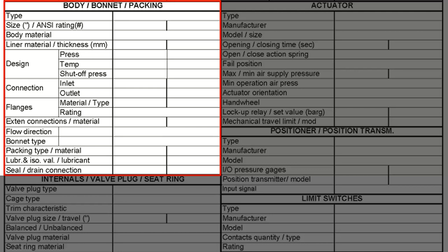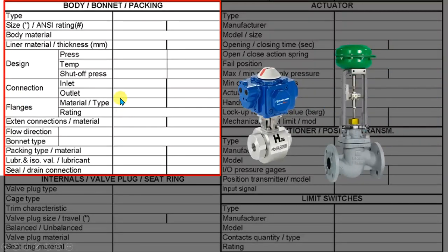In the European context, size and rating are usually expressed in DN millimeters and PN based on European standard EN 1092-1 — for example, PN 10 or PN 25. Body material is another important field selected by engineers to be compatible with the process, including pressure, temperature, and medium compatibility. The design data represents the maximum conditions the valve is rated and tested to work in. Connection can be specified as flange, butt weld, or socket weld. Threaded connection is also common for smaller valves up to two inches.